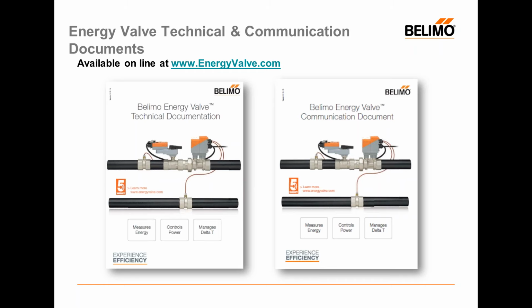Okay. Next question. Is there a way to discover the IP address for a currently installed Energy Valve? Yes, there is, and that is again by using our ZTH US tool. The ZTH will actually go into the Energy Valve, download its settings and configurations, and one of the things that will populate on the two-line LCD of the ZTH is going to be the IP address. So if for some reason you misplaced or lost the IP address, or taken over a job with an existing Energy Valve and you don't know the IP address, you can use our ZTH to find that.